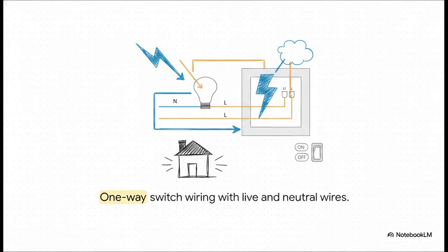Take a look at the wiring layout for a simple one-way light switch here. Notice how the circuit flows. The live wire, represented by that L terminal, supplies the flow of electricity right into the switch. When you flip that switch, the internal contacts meet, and current travels out through the L1 terminal directly to the light bulb, lighting up your room. Finally, the neutral wire, labeled N in blue here, carries that current safely back to the panel to complete the circuit. It's really just a beautiful, elegant loop.